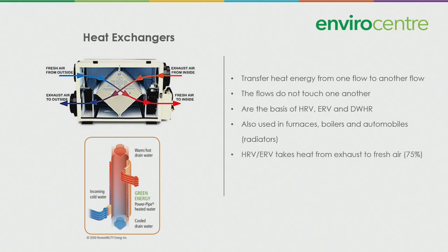Getting back to HRVs and ERVs, they take heat from the exhaust air and put it into the fresh air coming into the building, recovering about 75% of the heat—so they're actually pretty efficient. A drain water heat recovery unit is up to about 60% efficient; it does a similar thing, taking heat from your drain water and putting it into the inlet water heading into your water heater.